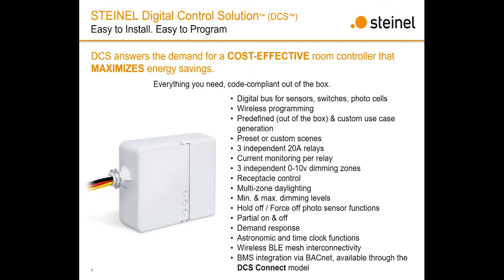You can't do multiple voltages, so a 120 volt and a 277 volt with a single 20 amp relay, and you can't do a plug load control and a lighting load with a single 20 amp relay. And last, you obviously cannot exceed that 20 amps worth of lighting. With this DCS, you can do all of that. So 3 20 amp relays adding up to 60 amp control. We can do a 120, a 277, all with a single DCS, as well as plug load control and a lighting load with a single DCS.